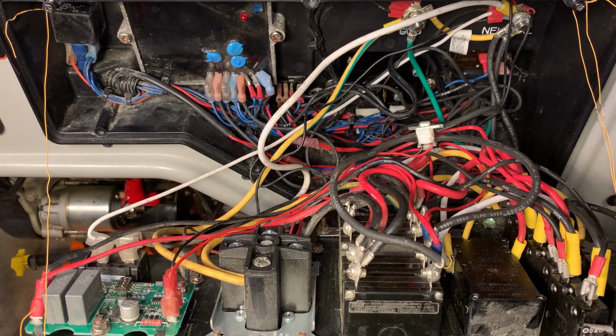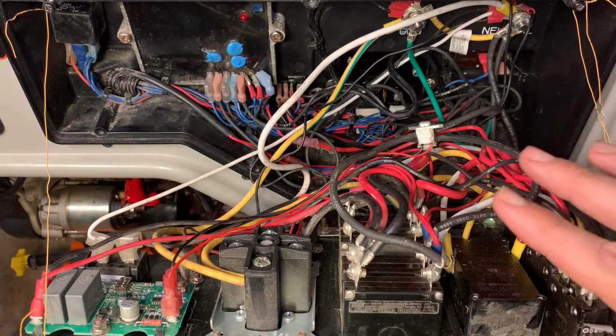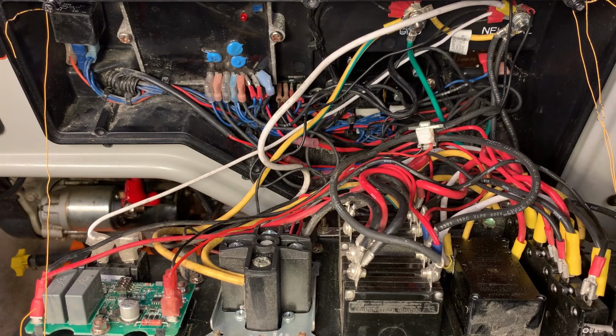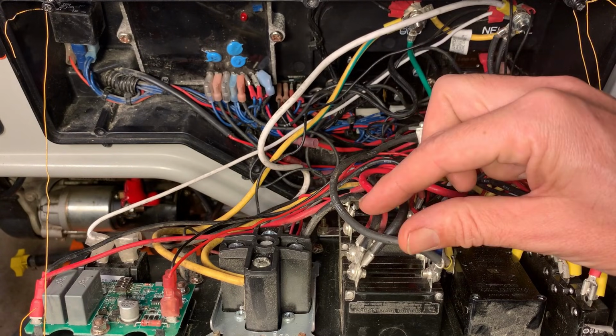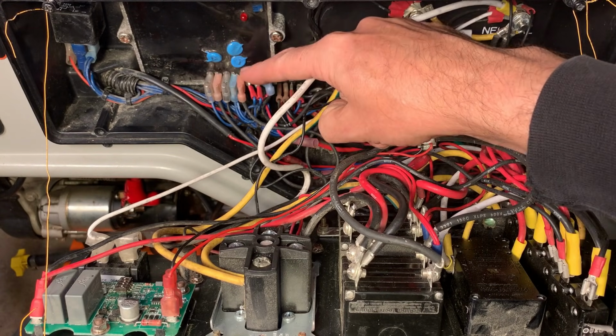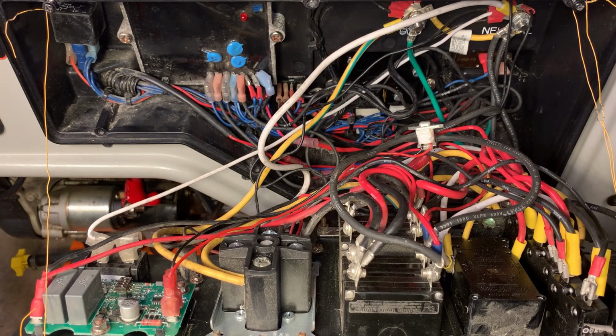Okay, got a game plan here. I don't have a service manual for this generator, but I do have one for a Generac Guardian series, and that has an extensive troubleshooting section. The principles in there can apply to many different types of generators. That manual suggests in this scenario—where we have a normal amp draw from the 12-volt battery into the rotor, and then we get over 60 volts out on the outlets and on the DPE, but nothing on the excitation winding—that the next place to go is testing the insulation with a high voltage tester.